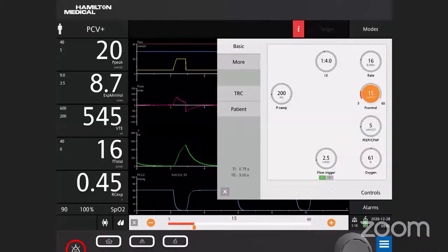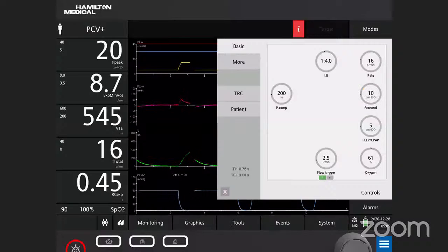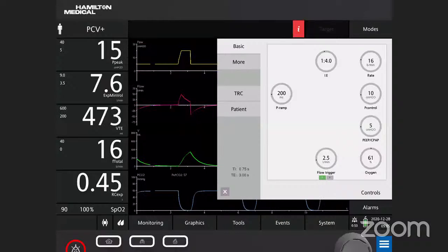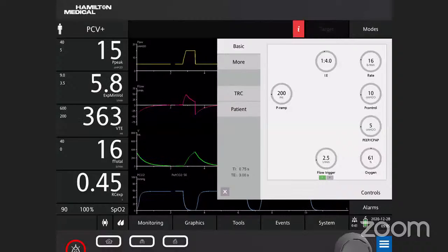come down on the pressure control level. And you have to observe the change that is happening in the tidal volume. So an accepted tidal volume you should aim for, right? Then you should set the rate, the PEEP level, the FiO2, the IE ratio, and ramp time in pressure control ventilation. The ramp time has a lot of terminologies being used, so we will call it the inspiratory rise time. That will be easier to remember.